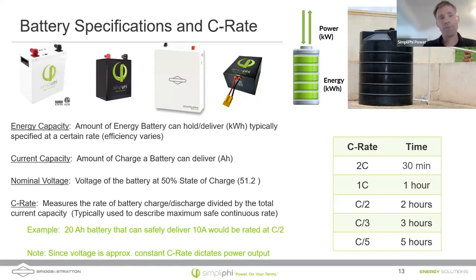Although if you take a voltmeter and measure the voltage on our batteries, a 48-volt battery would normally be above 48, and a 24-volt battery would be above 24 volts. It will reach those values, but the voltage of the battery changes depending on its state of charge. So the nominal voltage is the named voltage. It is also commonly referred to as the voltage of the battery at a 50% state of charge. I'm going to use that definition of nominal voltage. For our 48-volt batteries, it's 51.2, and for our 24-volt batteries, it's 25.7, I believe, or 25.6.